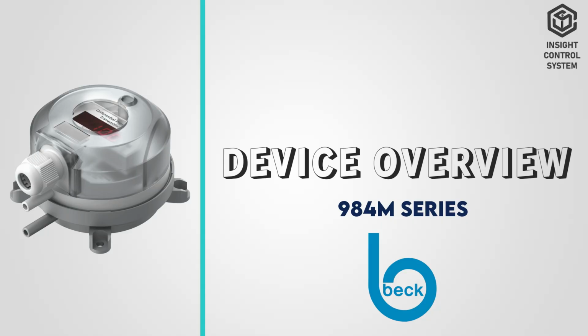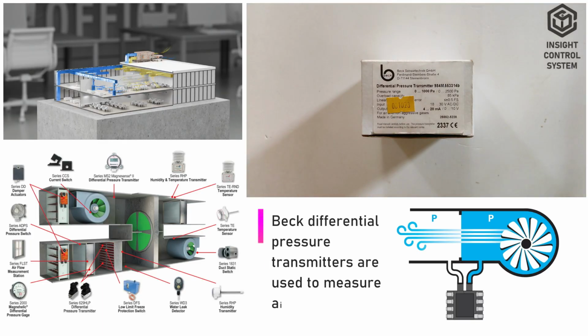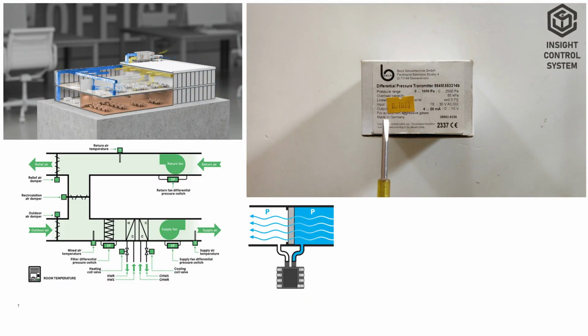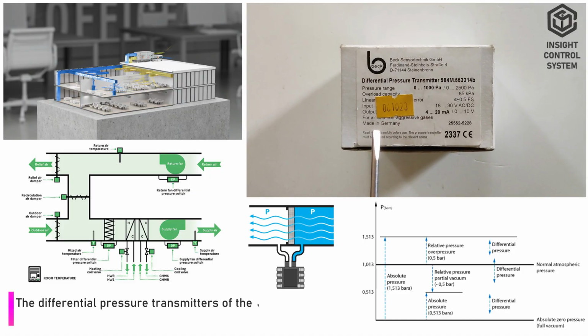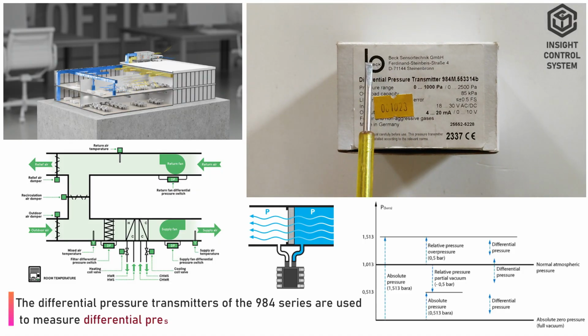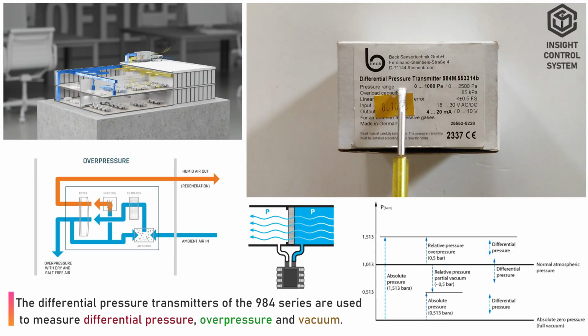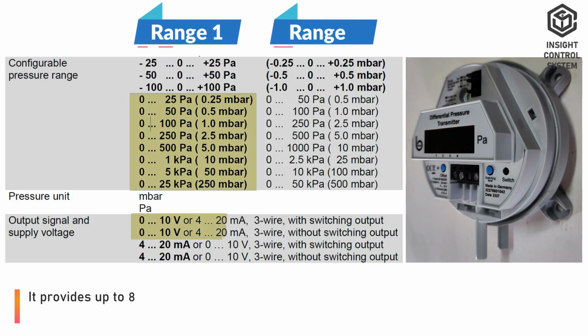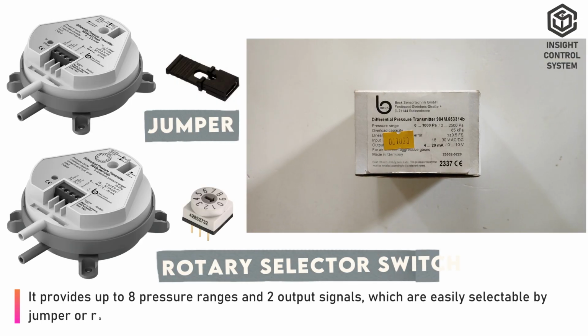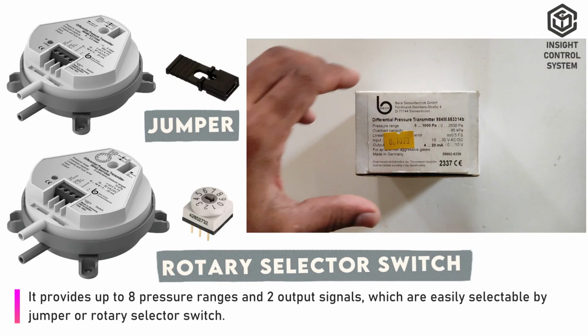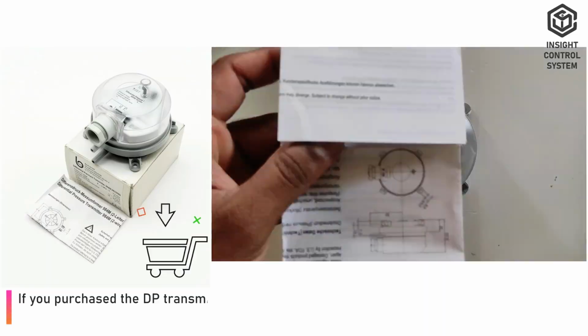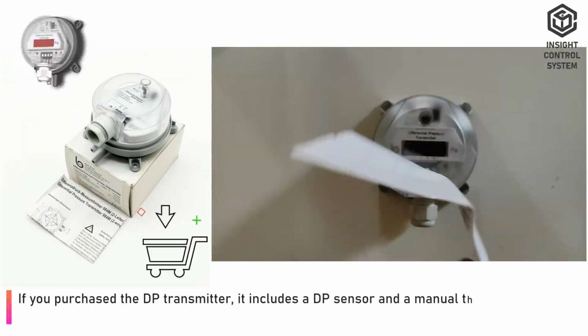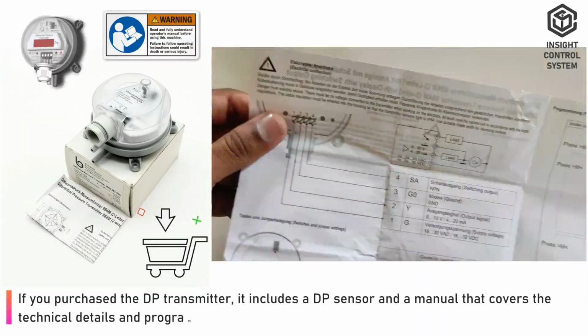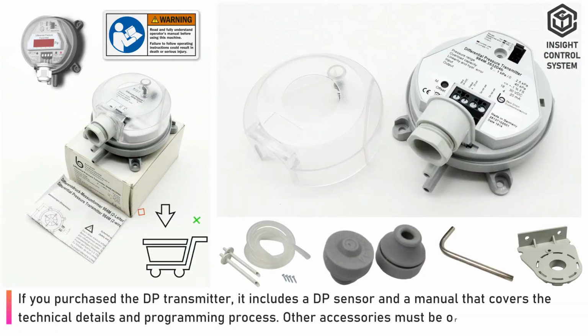Device overview. Beck differential pressure transmitters are used to measure air applications. The differential pressure transmitters of the 984 series are used to measure differential pressure, overpressure, and vacuum. It provides up to 8 pressure ranges and 2 output signals, which are easily selectable by jumper or rotary selector switch. If you purchase the DP transmitter, it includes a DP sensor and a manual that covers the technical details and programming process. Other accessories must be ordered separately.